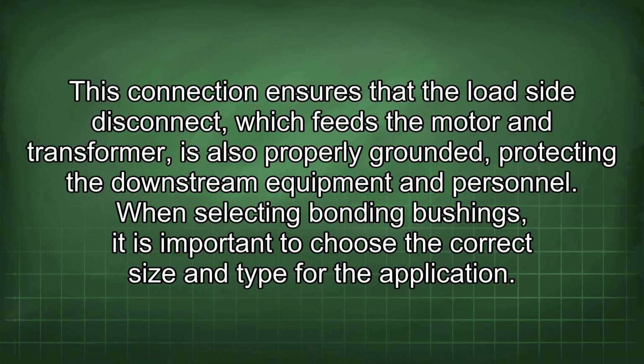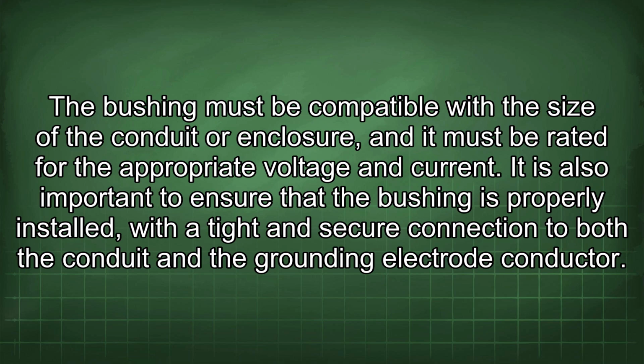downstream equipment and personnel. When selecting bonding bushings, it is important to choose the correct size and type for the application. The bushing must be compatible with the size of the conduit or enclosure, and it must be rated for the appropriate voltage and current. It is also important to ensure that the bushing is properly installed with a tight and secure connection to both the conduit and the grounding electrode conductor.